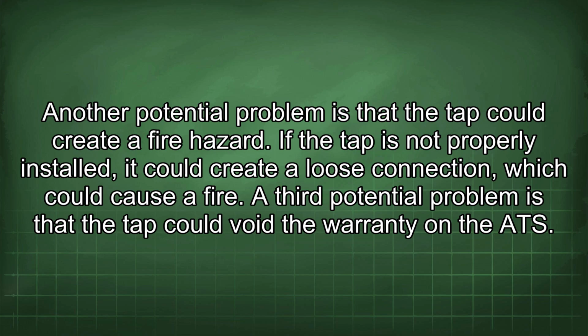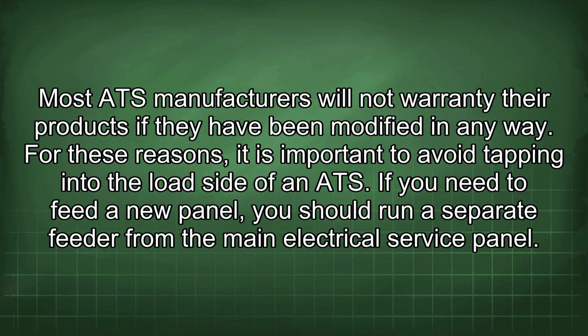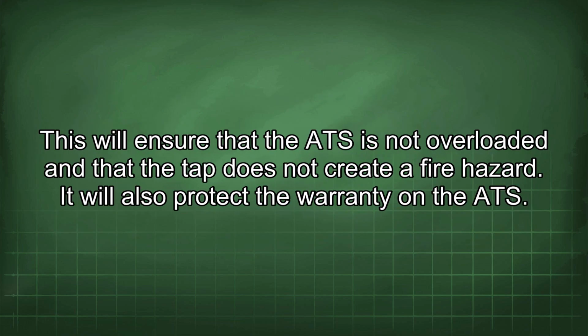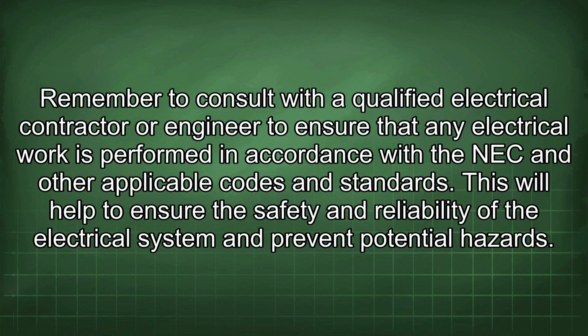A third potential problem is that the tap could void the warranty on the ATS. Most ATS manufacturers will not warranty their products if they have been modified in any way. For these reasons, it is important to avoid tapping into the load side of an ATS. If you need to feed a new panel, you should run a separate feeder from the main electrical service panel. This will ensure that the ATS is not overloaded and that the tap does not create a fire hazard. It will also protect the warranty on the ATS. Remember to consult with a qualified electrical contractor or engineer to ensure that any electrical work is performed in accordance with the NEC and other applicable codes and standards.